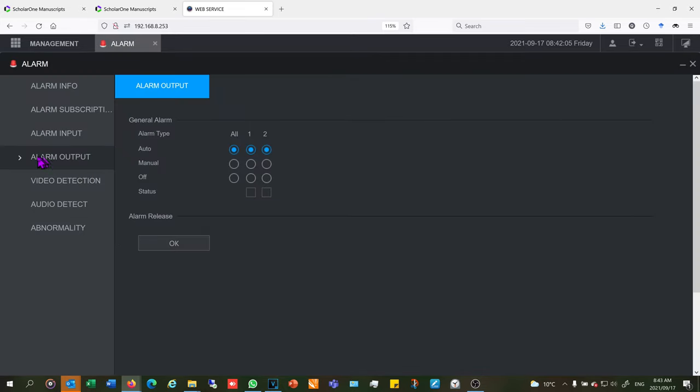Just make sure that on your alarm option when you go to alarm output, make sure that these toggle buttons are switched to auto. If it is off it will override your alarm output and therefore your bell won't ring. So if yours doesn't work just have a look over here at alarm output.